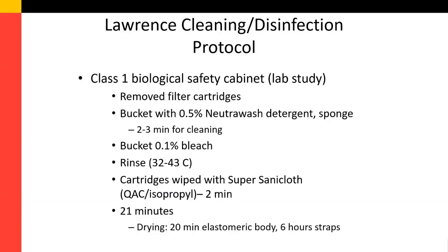In this study, which was a laboratory-based study, they performed their cleaning and disinfection protocols in a Class 1 biological safety cabinet. First, they removed the filter cartridges. They put the respirators in the face masks in a bucket that was filled with 0.5% Neutrawash detergent and gently cleaned the respirators with a sponge.